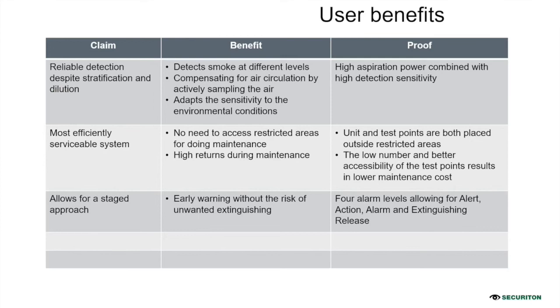For the dust, we have different kinds of filters available. So if the HVDC is dusty, these filters can arrest the dust, and only the air goes inside and gives you the proper detection. If you talk about serviceability, the test points are outside. The detection panel is outside the area where the high voltage is present, so you have no chance of any mishappening or malfunctioning. So we always recommend going with aspirating smoke detectors for this HVDC application.